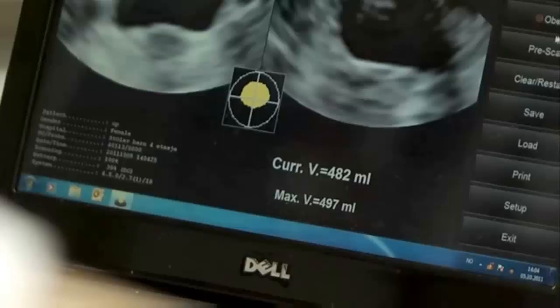The yellow image of the bladder should be in the center of the crosshair. Curr.v means current volume. Max.v means maximum volume. They may be different if several scans are made for the same patient.